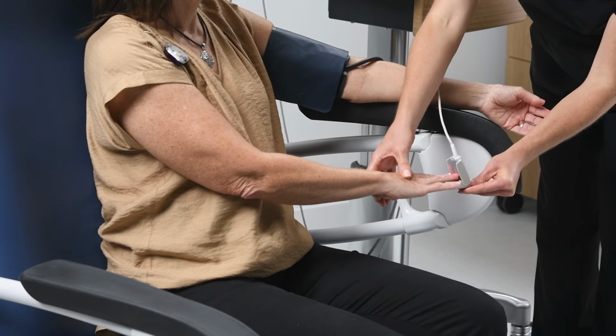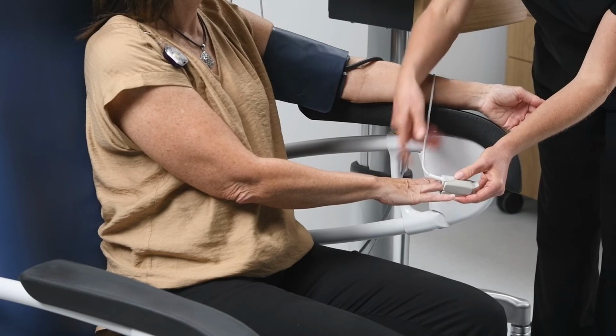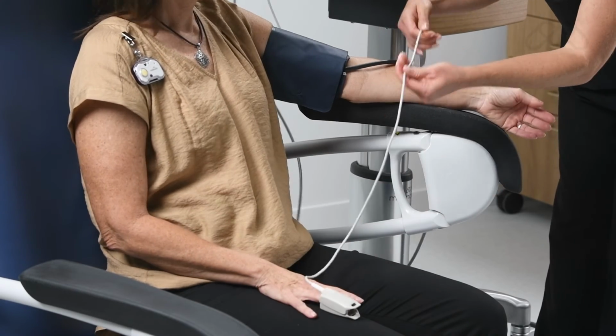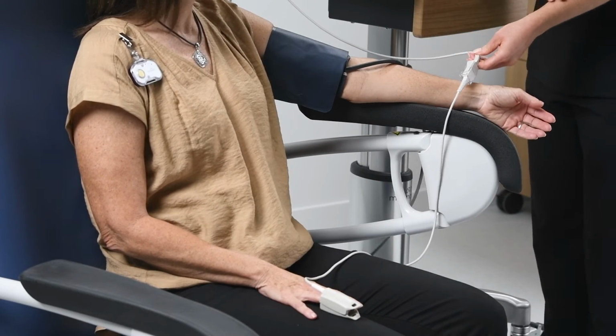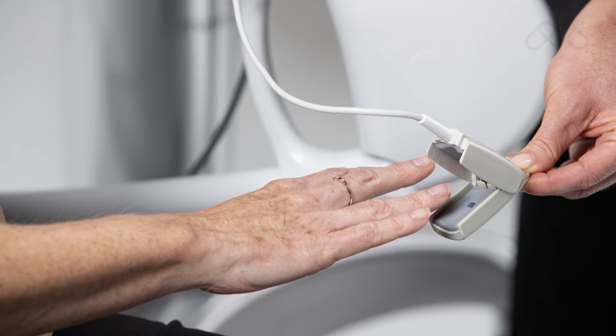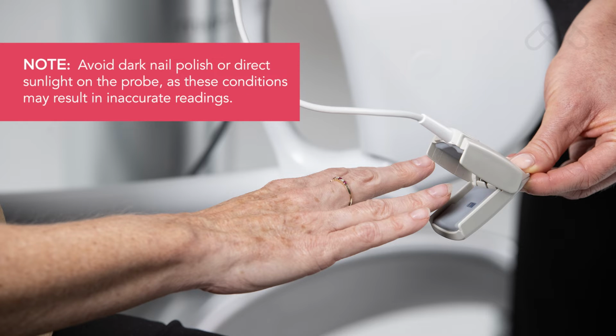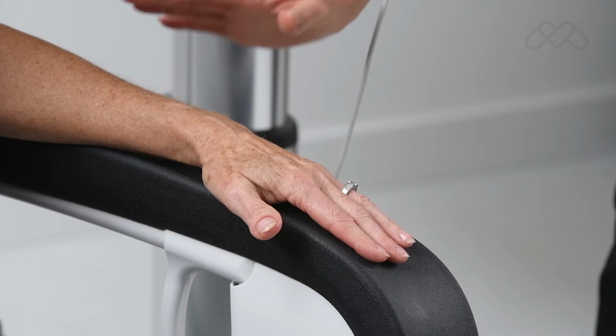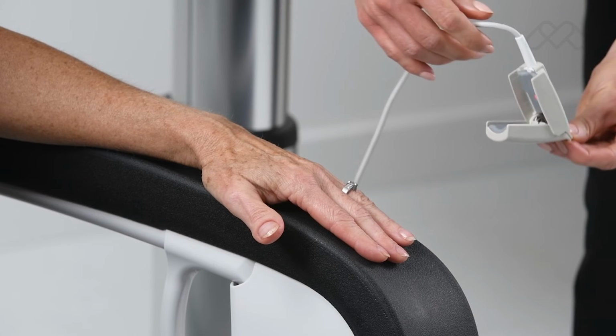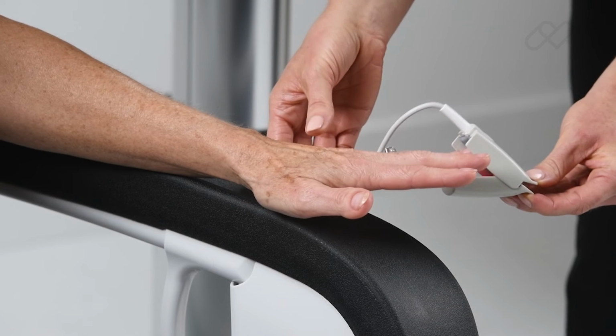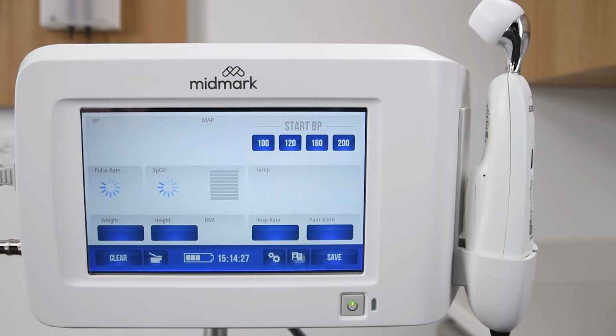If the blood pressure measurement is occurring simultaneously, place the finger clip sensor on the limb opposite the one with the blood pressure cuff. Avoid using the sensor with dark nail polish or direct sunlight on the probe, as these conditions may result in inaccurate readings. When the SpO2 sensor is attached to a patient's finger, an audible tone will sound and the in-progress wheel will appear on the vital signs device screen.